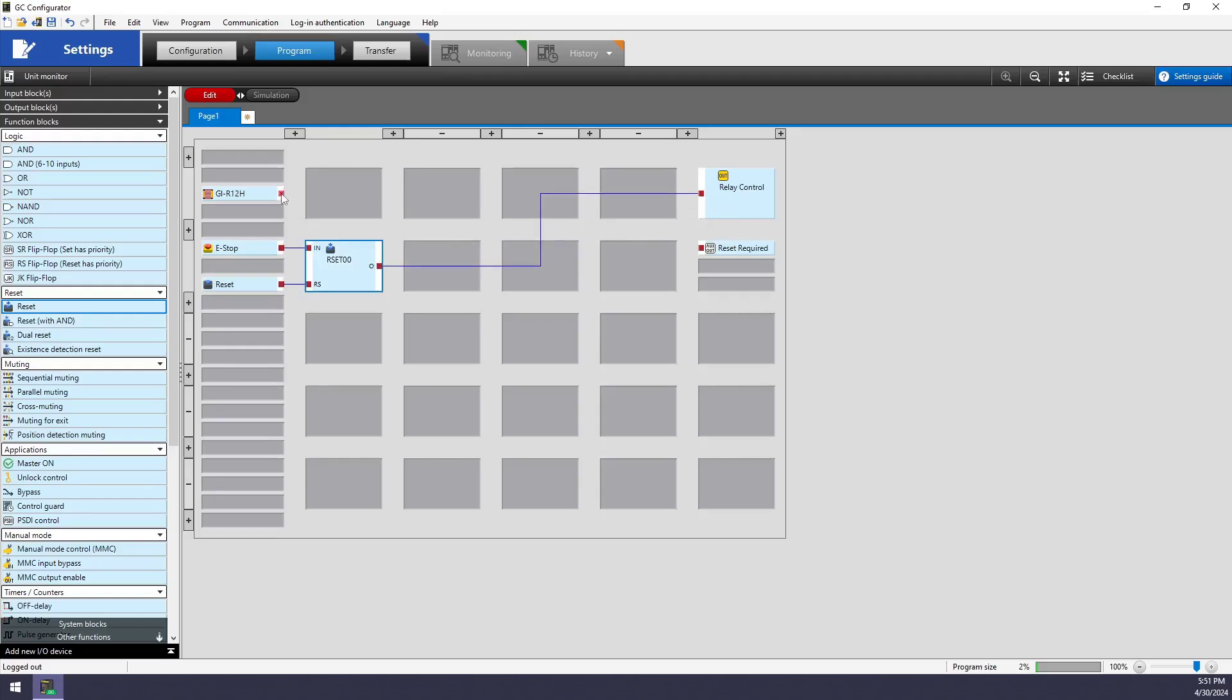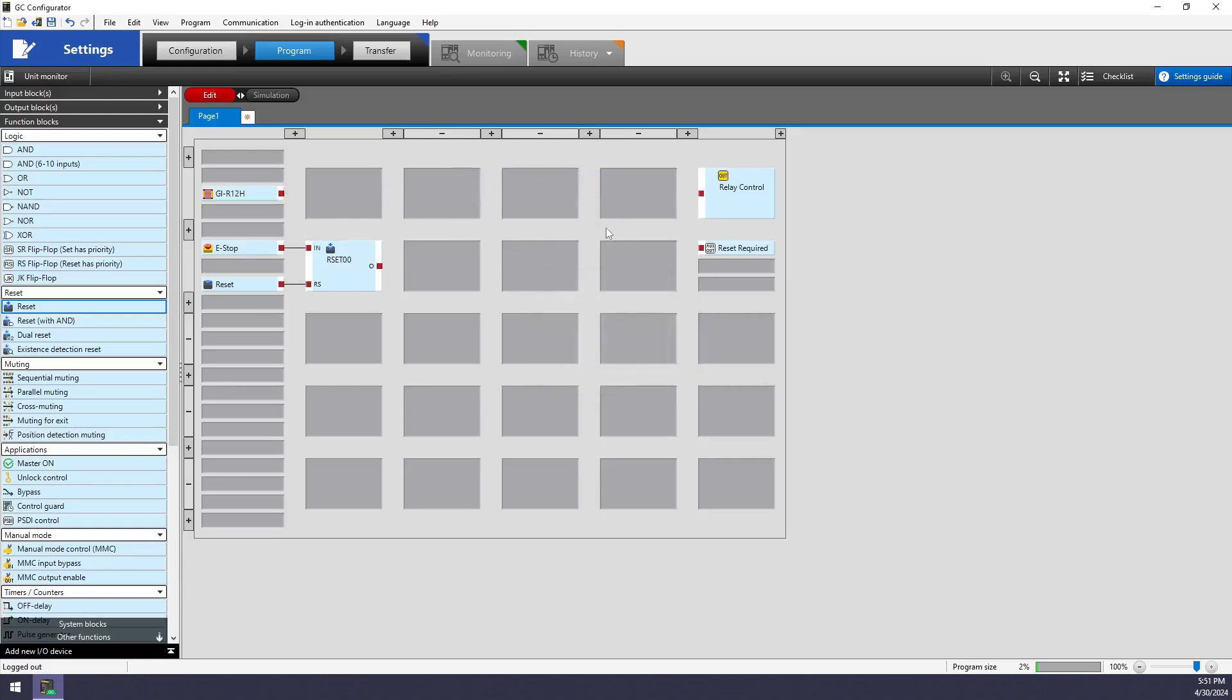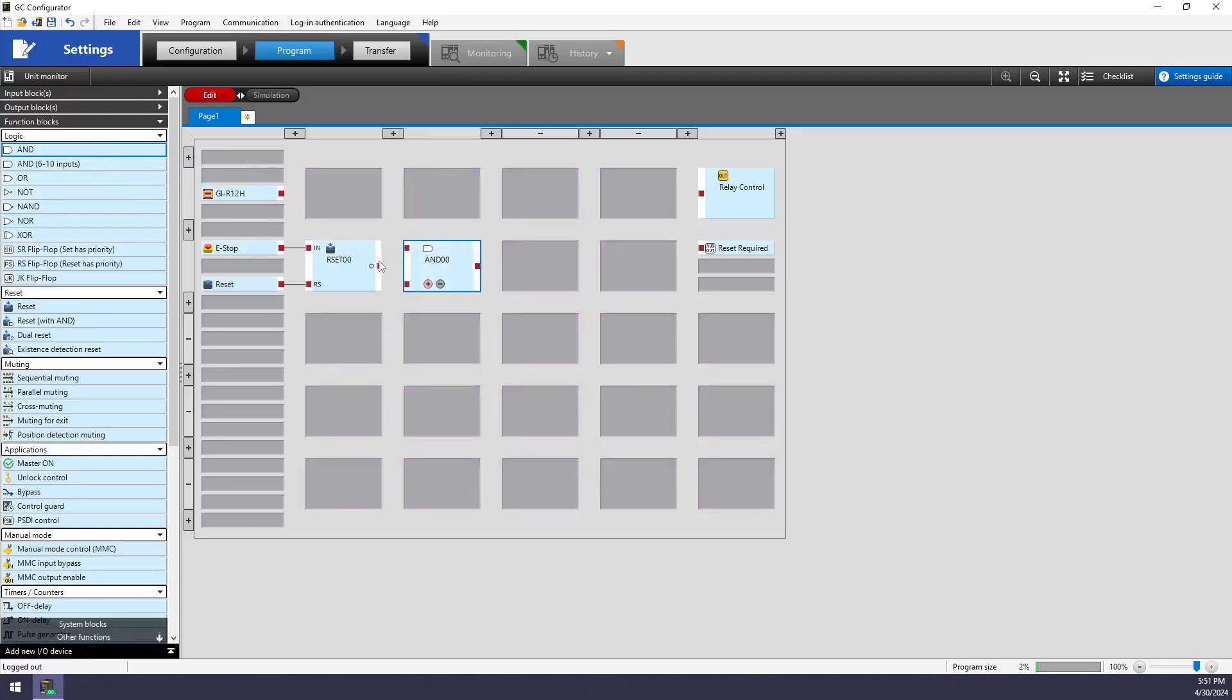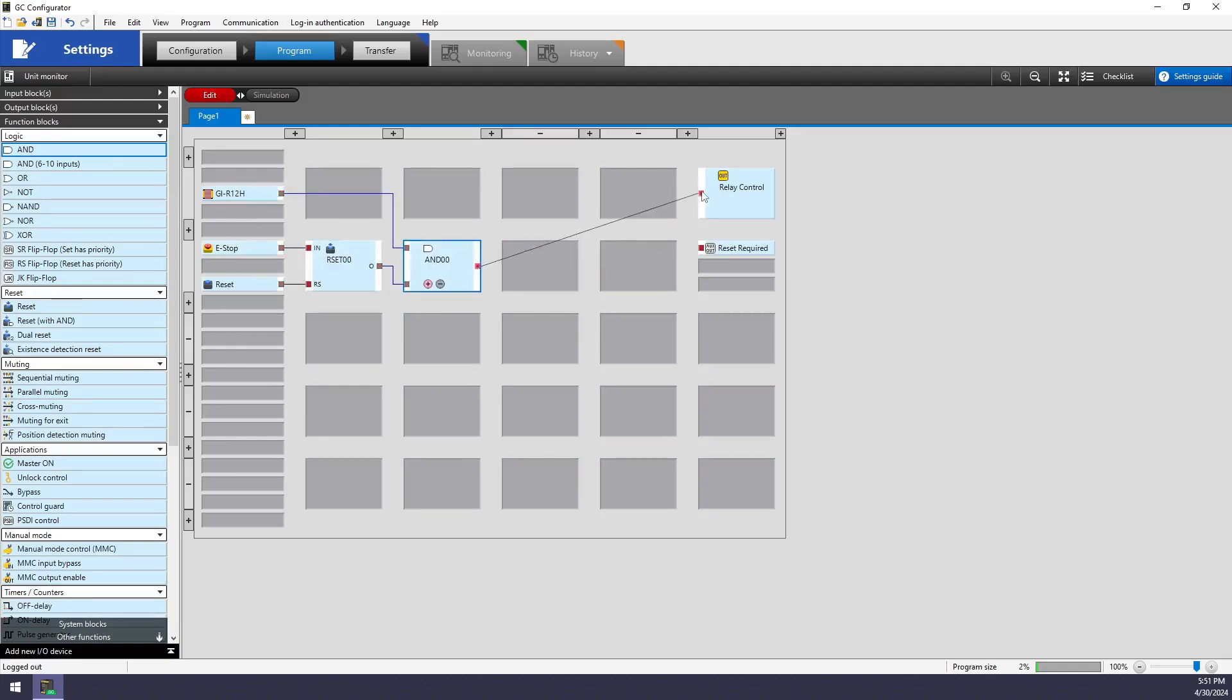I'm ready to tie the output of this function block to my safety output, but I also want my light curtains to control that. I can't have both of them going there at the same time. So what I need to use is this and block here. So I say if my reset tied to my e-stop is happy and if my curtains are happy, then I can toggle my safety output.